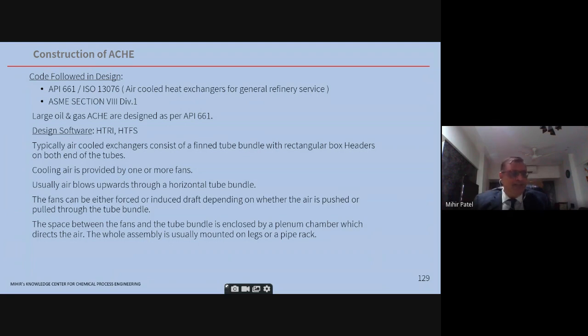You can have small ACHEs also. For example, our car radiator is nothing but an air-cooled heat exchanger. But that doesn't have to be as per API. It is a manufacturer standard. Similarly, an air compressor supplying plant air or instrument air has an air-cooled exchanger. You don't want that as per API 661. That's very costly. You can go with manufacturer standard there. Design software used is HTRI, HTFS. Okay, so these are the different things.